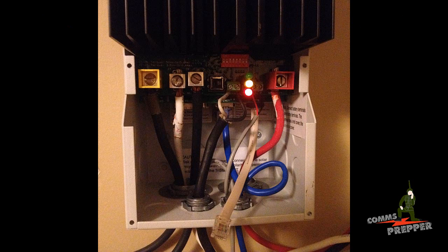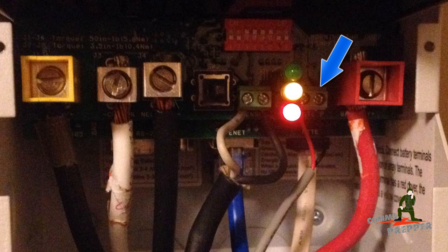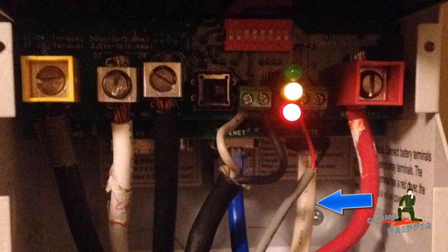We hooked up some of the other options on the TS-MPPT-60 charge controller. The first thing we hooked up here was the remote battery voltage sense, marked with the blue arrow. Then we added the remote temperature sensor, which is also connected to the battery. And then we added the Ethernet connection to the router out at the retreat location to give us Internet access to the charge controller.